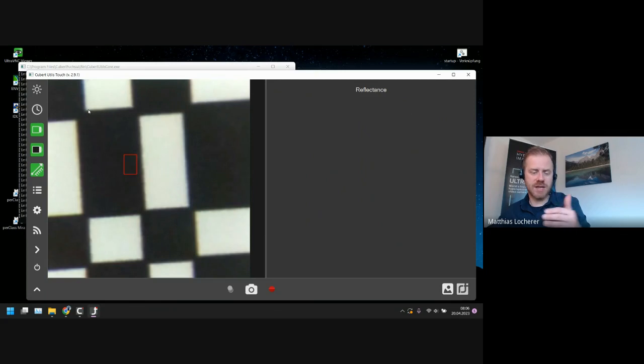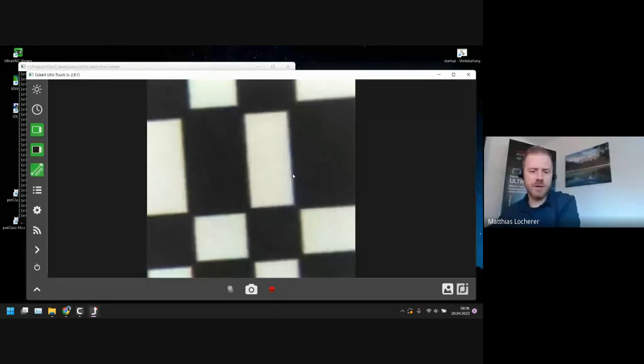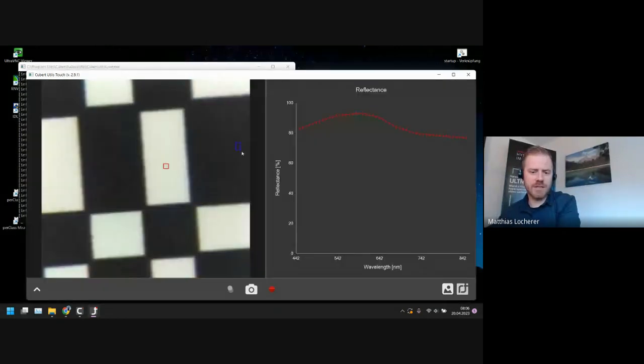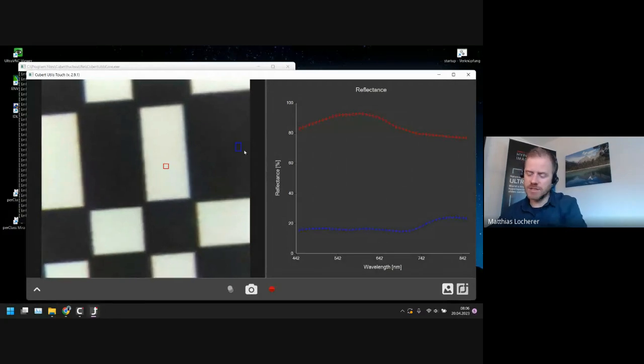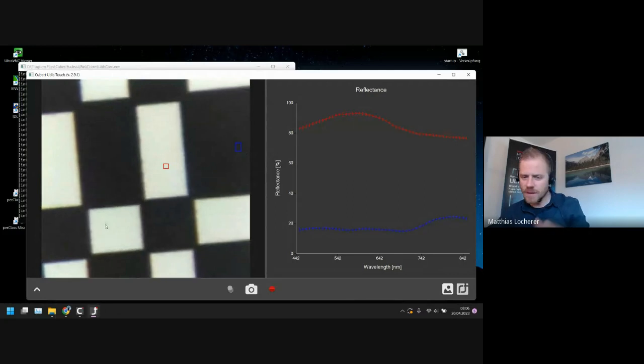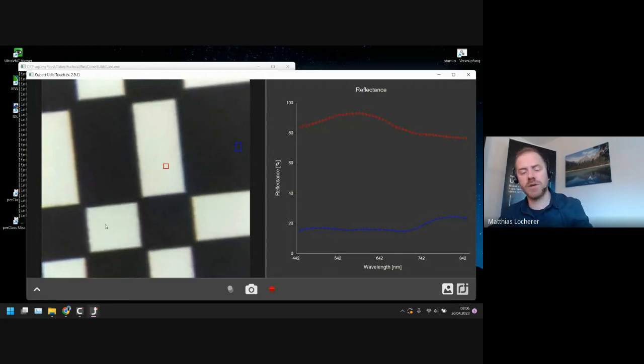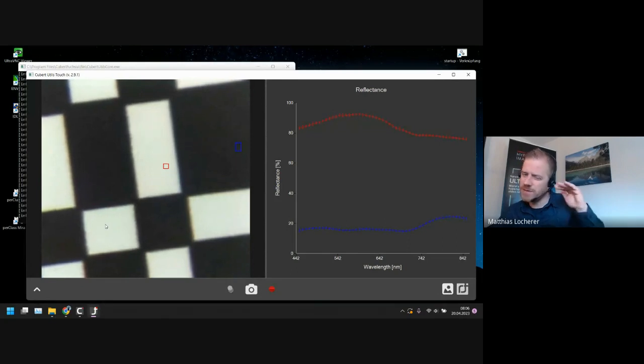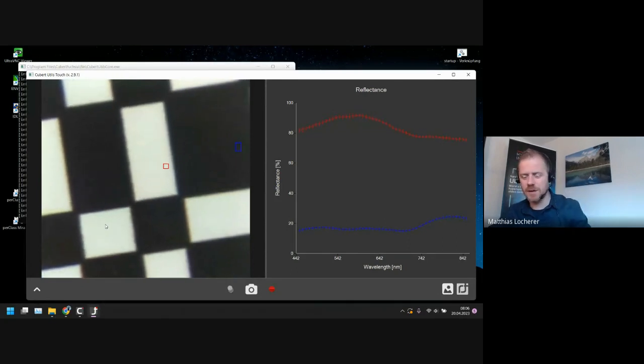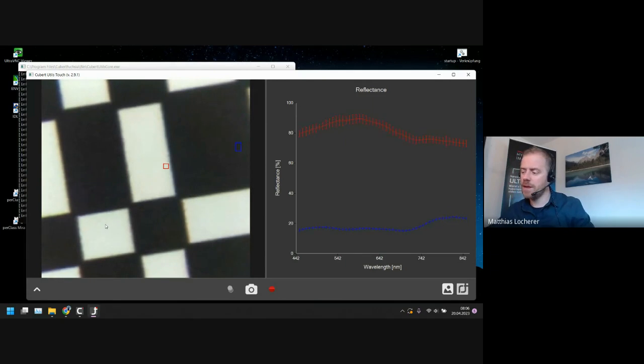And it is then aligning all the spectral bands accordingly, with a clear output. You have the white fields or black fields as well, without any distortions. By the way, you see a tiny oscillation in the spectral graphs. That is because of the 50 Hertz power supplies. The light source is not stabilized at the moment. So we have tiny variations in brightness, which is absolutely normal.